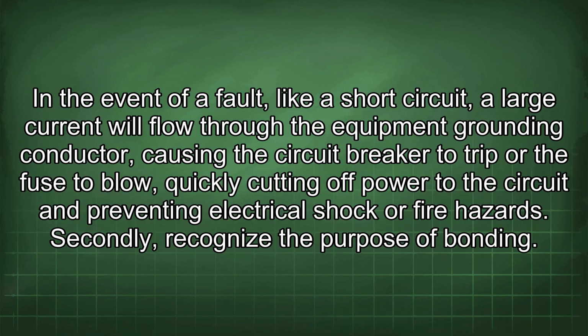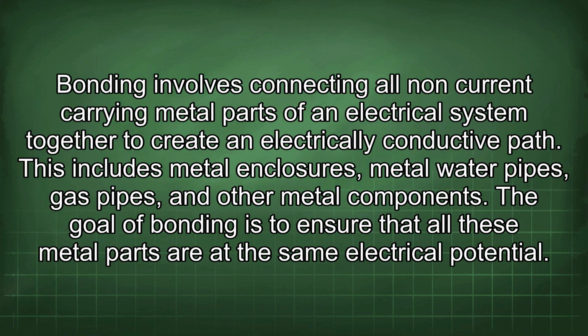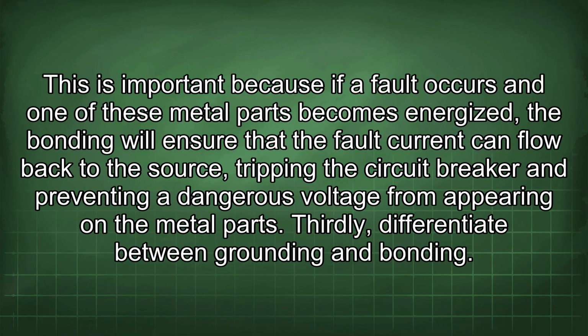Secondly, recognize the purpose of bonding. Bonding involves connecting all non-current carrying metal parts of an electrical system together to create an electrically conductive path. This includes metal enclosures, metal water pipes, gas pipes, and other metal components. The goal of bonding is to ensure that all these metal parts are at the same electrical potential. This is important because if a fault occurs and one of these metal parts becomes energized, the bonding will ensure that the fault current can flow back to the source, tripping the circuit breaker and preventing a dangerous voltage from appearing on the metal parts.